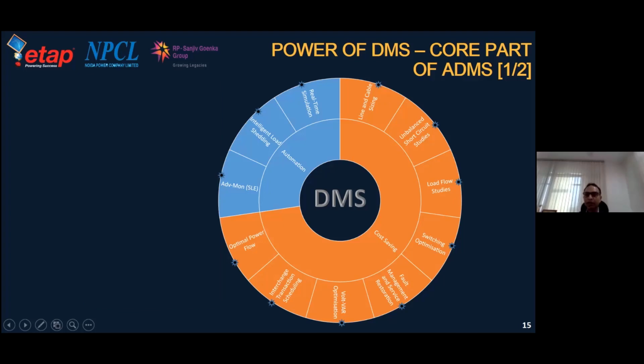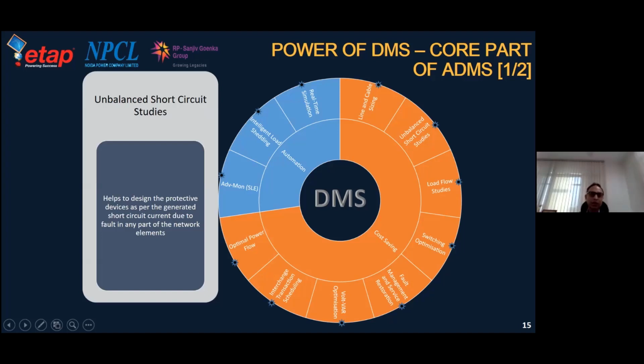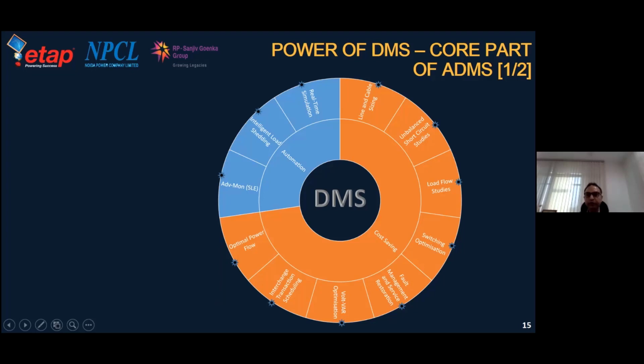This UBLF, unbalanced load flow and short circuit studies, helps to design the protection arrangement or protection scheme, and accordingly helps us decide on the protective devices about their rating and fault current carrying capacity, etc., at different network node levels.